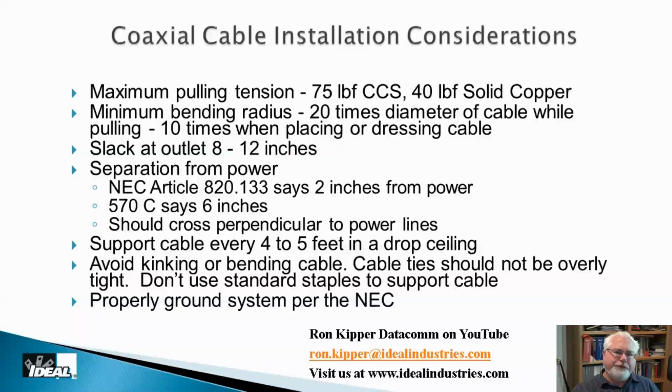Separation from power is always a good one to ask folks, and anytime you see a number, it's more or less an opinion by some standard body or something like that. The only thing that is law is the National Electric Code, and it says 2 inches. Now, we know we like to say typically a lot further away than that. And I tell folks, as far away as you can get it is the best answer you can give people. But 2 inches is what code recommends. Now, if you look in the residential standard, the 570 standard, it's going to say 6 inches on coax, okay?